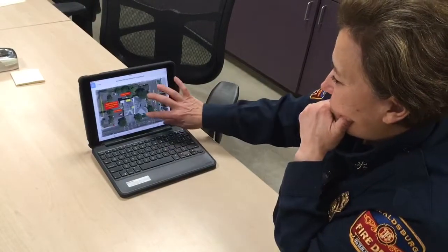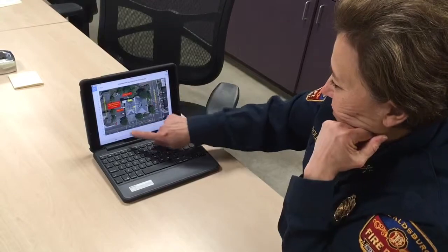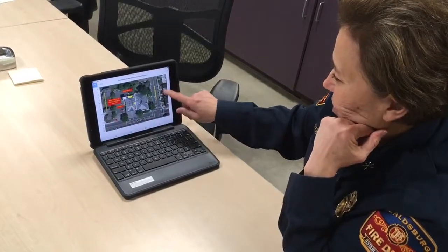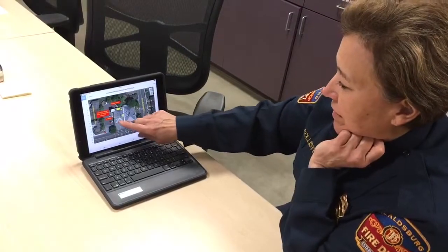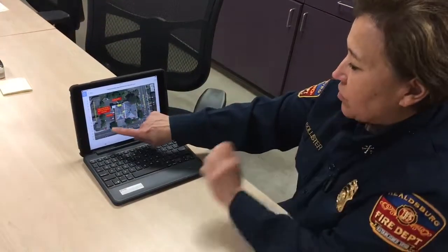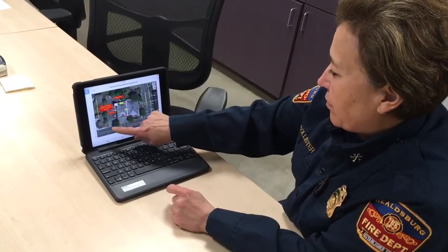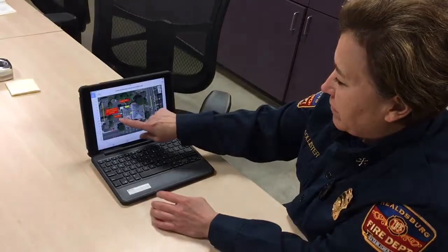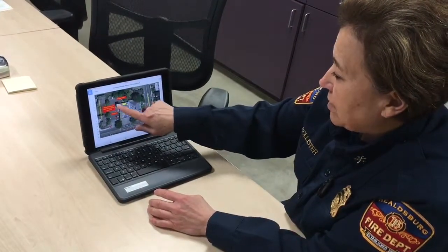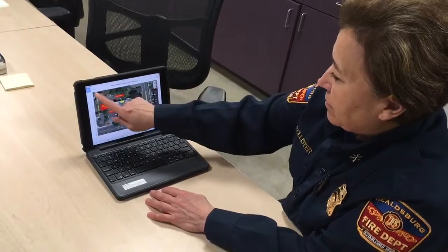And so here it is. It has the date. It has the scale down here. It has the direction north. It has the facilities next door. It has the streets, and it has the areas. The storm drains are marked. The fire department, like the fire hydrants and things we'd want to know. Gas shut off. But the tool room, the diesel tank, the oxygen room, which we all saw. So I would say I would accept this map.